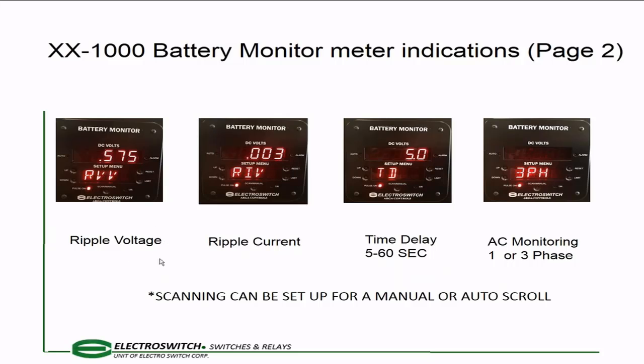This gets into monitoring the ripple voltage. You can see it's 575 millivolts. Your ripple current is 3 milliamps. The time delay I can set from 5 seconds to 60 seconds. For your chargers, you can have a single-phase or a 3-phase, and you have to make sure you identify what your charger is doing. If you have a single-phase charger and I set it to 3-phase, I'm going to read 3 times the ripple voltage and ripple current, so I'm going to get an alarm immediately. So it's important to make sure it's properly set.